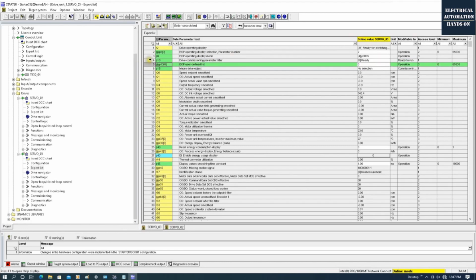0 means ready. And this is Servo 2. And we will do the same thing for the Servo 3. All the settings are the same. I won't show this process again. Just keep in mind, when you set the Servo 2 or Servo 3, you need to make sure you are selecting the right sheet here. In some cases, maybe you switch to the wrong sheet and set the wrong motor, the wrong target. So keep in mind, when you set motor by motor, you better set one by one. Otherwise, maybe you accidentally select another one and set the wrong parameter for that motor.